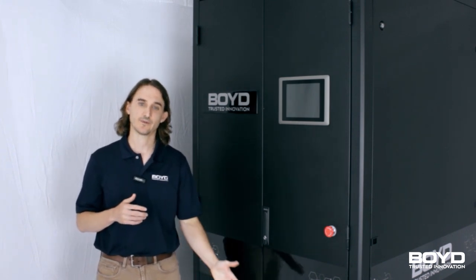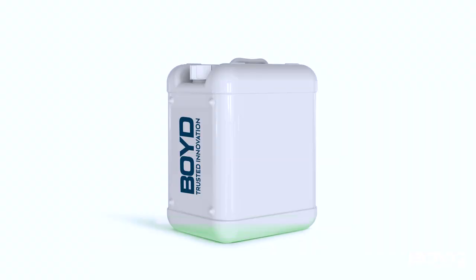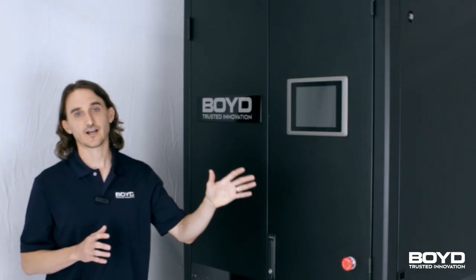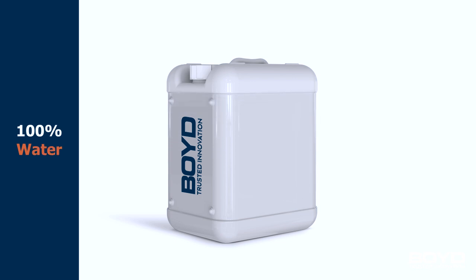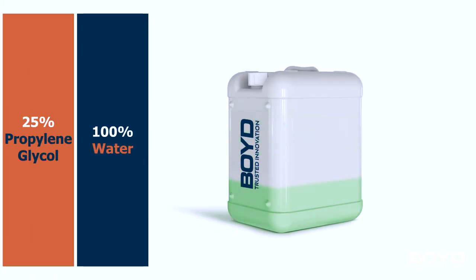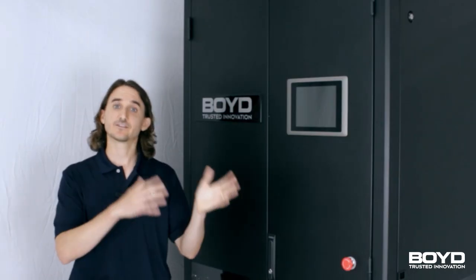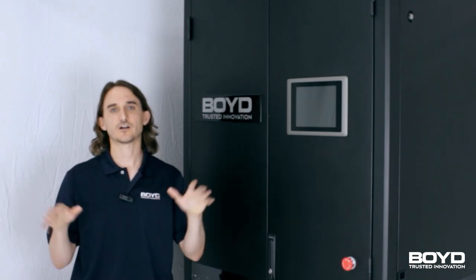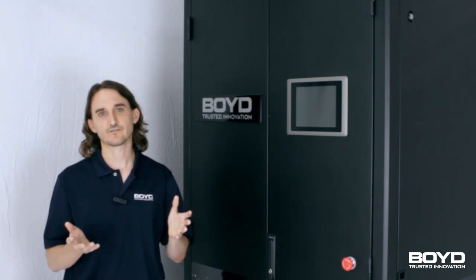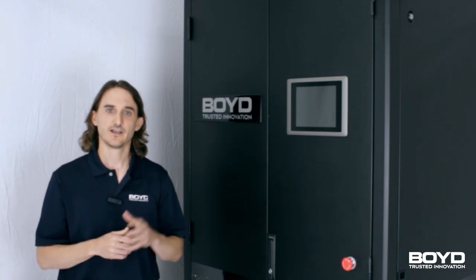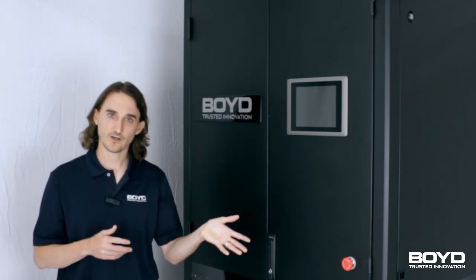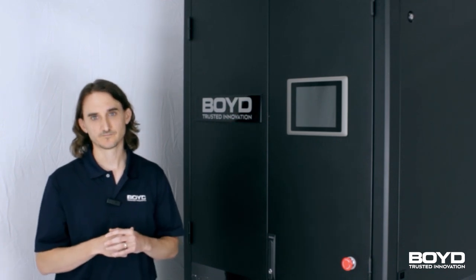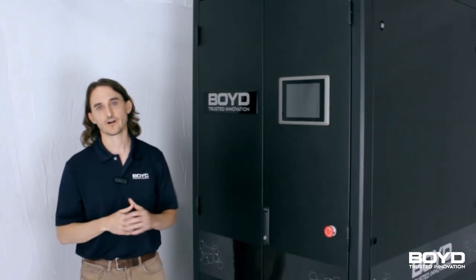We have 2 pumps, a makeup pump and a fill pump, that you can connect to a bucket, a drum, or any sort of tote that holds water or PGW. The secondary side is designed to run on 100% water or 25% propylene glycol water, and the facility side is designed for 100% water. Back to the sensors. Our sensors are all hot swappable. The pressure sensors are on Schrader valves to enable easy replacement, and the thermocouples are in thermal wells to allow easy replacement as well. Everything is on connectors, so there's no rewiring anywhere in the system.